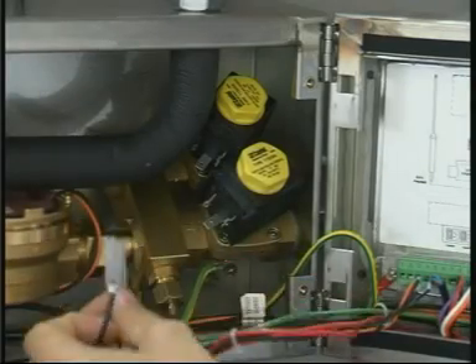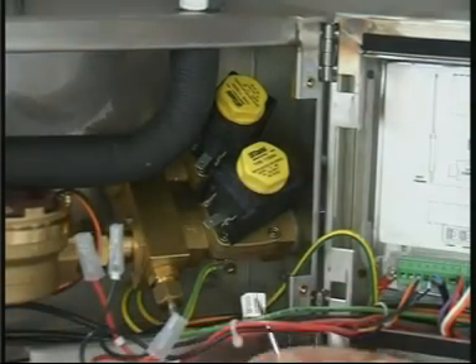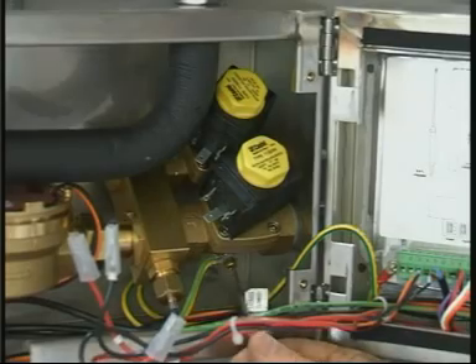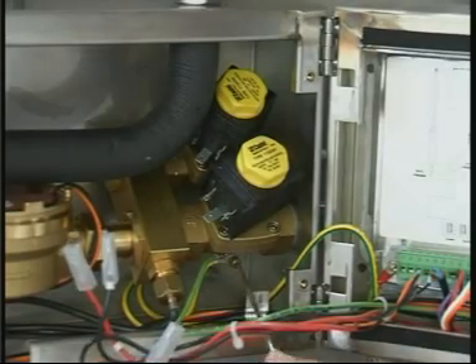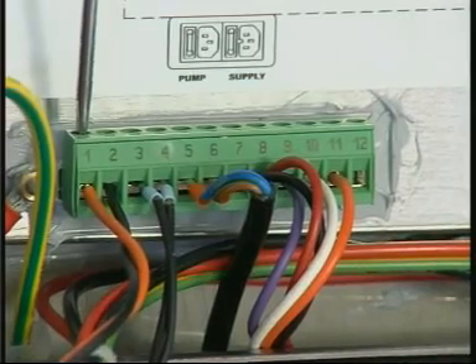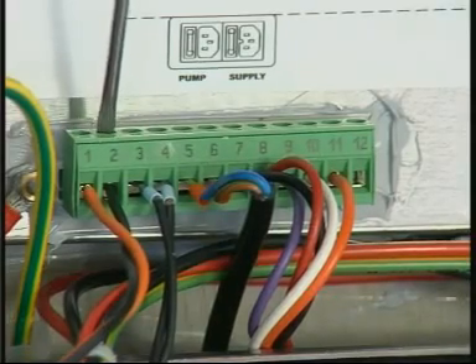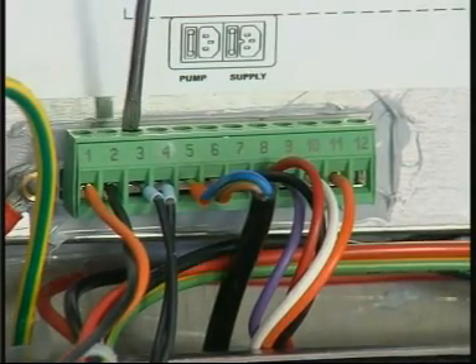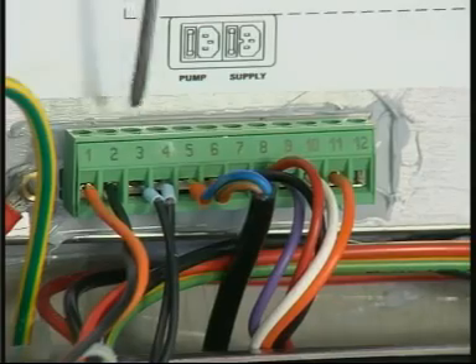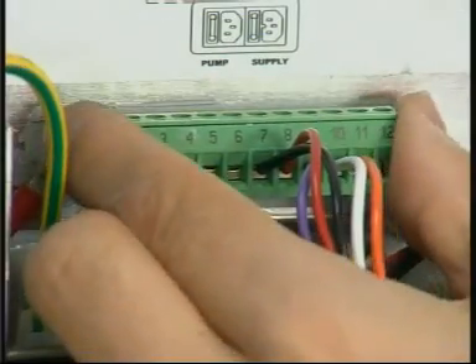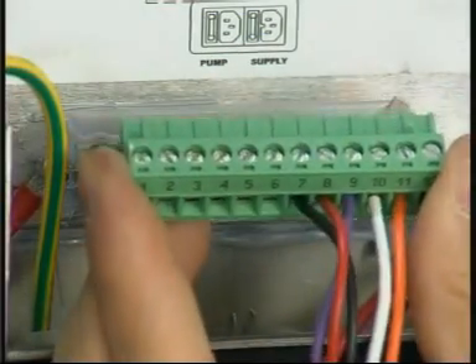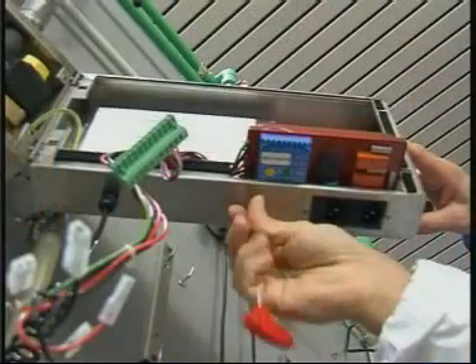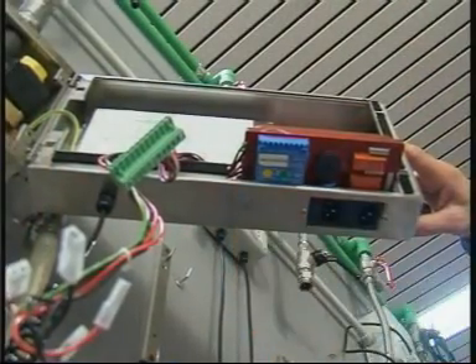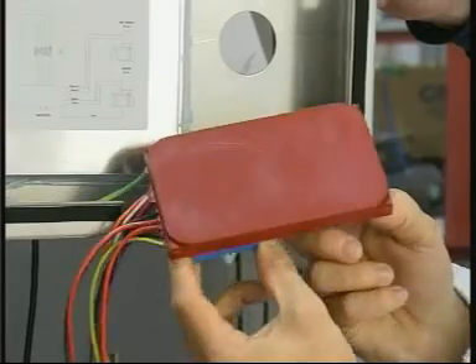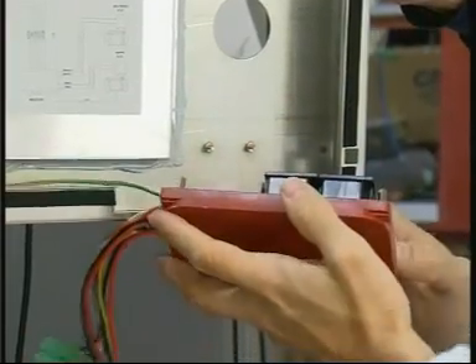To replace the board, switch off the supply to the machine and unscrew the fastening nuts from the protection of the power board. Disconnect the wires from the coils. Remove the earth screw. Disconnect the litre counter and the probes. Remove the terminal block. Unscrew the power board fastening screws from the cover. Extract the board.